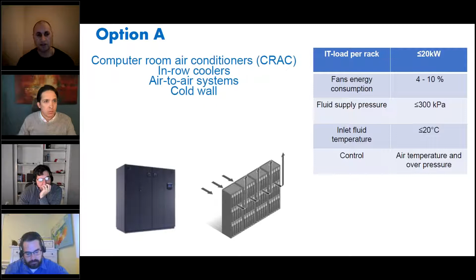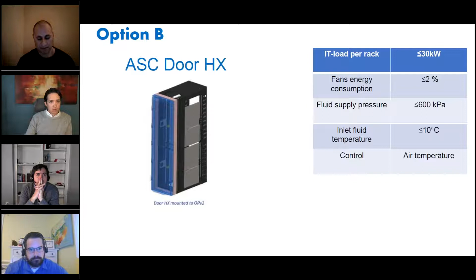In the case of backdoor cooling, we can increase rack capacity up to 30 kilowatts, but we are faced with low capacity of the heat exchangers themselves. For that reason, we need low temperature liquid with high flow rate, which decreases free cooling time and significantly increases pump energy consumption. Regarding price, it is more expensive as we need to use more reliable connections.